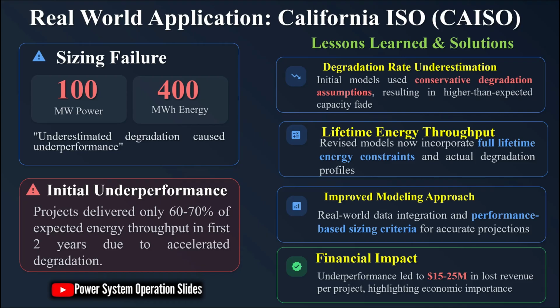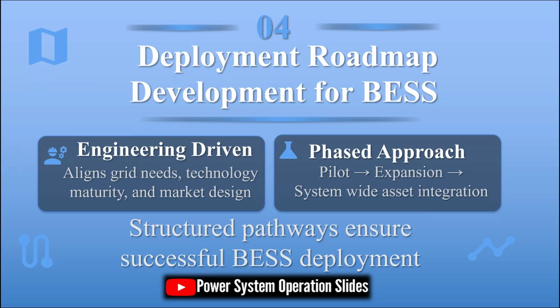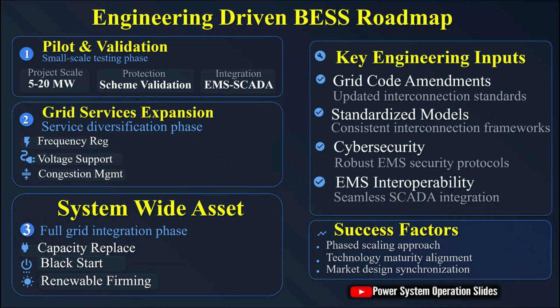deployments. Phase 2, the grid services expansion phase, involves scaling up BESS deployment to provide multiple grid services including frequency regulation, voltage support, and congestion management. During this phase, operators develop standardized procedures for BESS operation, refine control algorithms, and optimize the economic value through multi-service stacking. Phase 3, the system-wide asset phase, involves deploying BESS at GW scale as a core grid asset capable of providing capacity replacement, black start services, and renewable capacity firming. By this phase, BESS is fully integrated into system planning and operation, with standardized interconnection models, well-defined operational procedures, and mature market mechanisms.